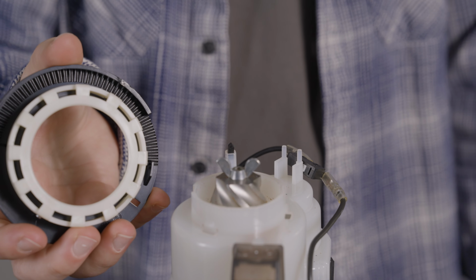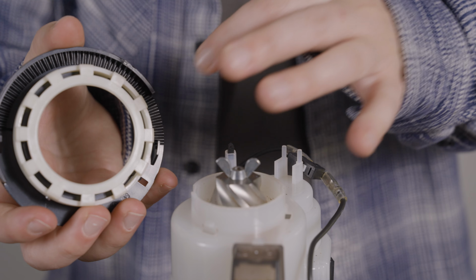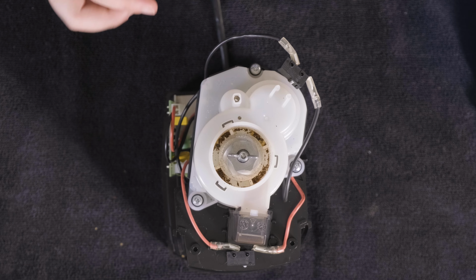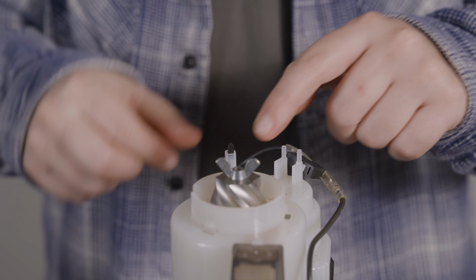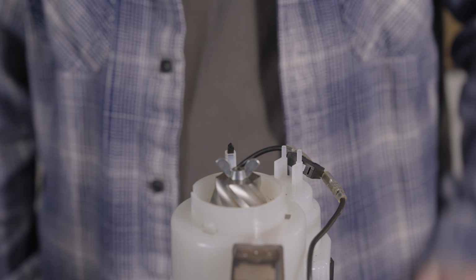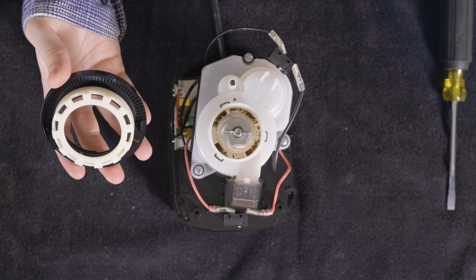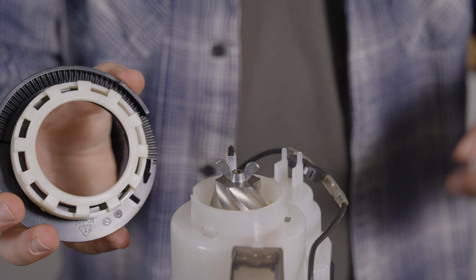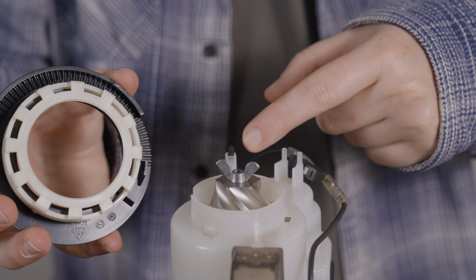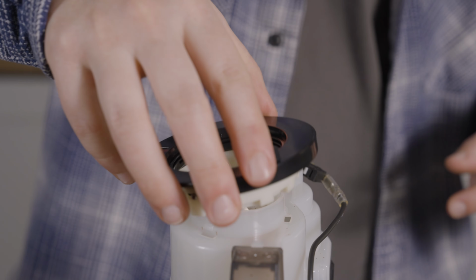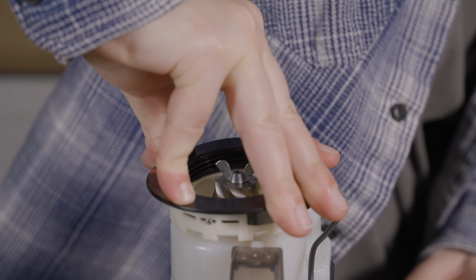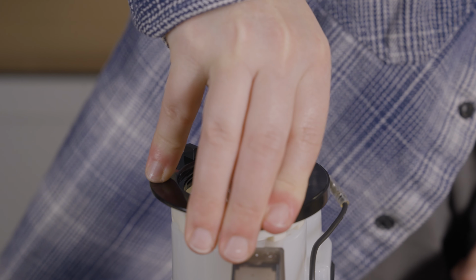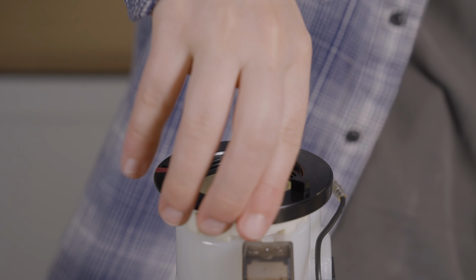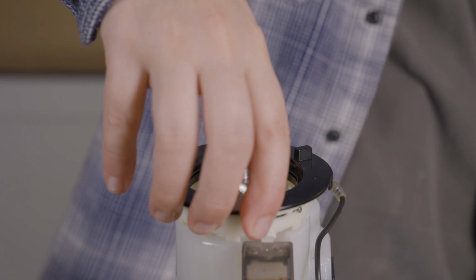Grab your new adjustment kit and get ready to set it in place. Confirm your spring is in place and the detent is positioned correctly, pointy side up. Set your adjustment kit in place by making sure that the detent is lined up inside the track. Press down firmly. There are 3 clips in the calibration ring that will all click into place. Once installed, double check when rotated that the detent clicks. It should feel firm, but rotate freely. Then you can place the micro switch back onto its posts.